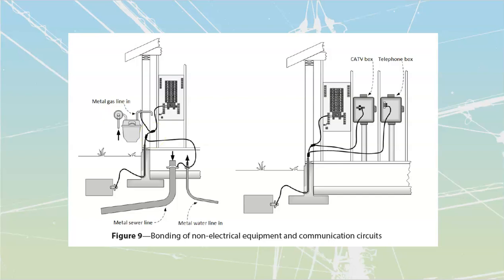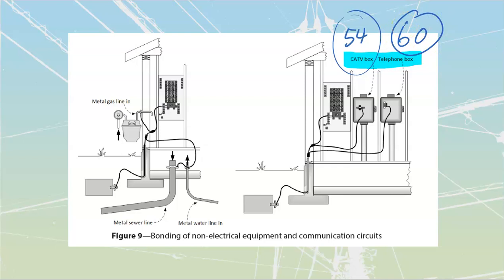The other ones that you should be familiar with are going to be my TV boxes and my telephone boxes. Telebox from BC Tel, Shaw boxes, any of those other ones that are going to be considered your CATV. These ones you are not going to find rules for inside of Section 10, but you're going to find the rules for this inside of Section 54, which deals with TVs and community antenna distribution. That's CATV. And these are going to be inside of 60, which is your electrical communications types of circuits. Once again, what we find inside of the code book, by the way, is going to be a minimum standard. What you discover inside of 54 and 60 will be very small sizes of wire that are going to be required to bond these components inside of there, blocking devices.